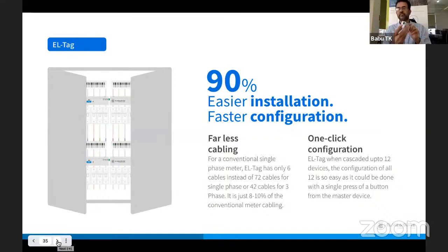Now on another side, you will find a 485 2-pin port. So you can loop several of these through and connect it to the master meter 485 which I showed you. Now look at the cabling. If you were to talk about 9 single channel meters placed in a panel and do the wiring, you will have about 72 cables moving around for these 9 individual channels of meter. As against this, one has only 4 on the voltage, 2 on the 485. If you talk about three-phase information, even then you needed 42 cables, whereas here you're only having 6 things. That 6, when I say it's pluggable, is very simple to do. You don't make a mistake of whether you are connecting the voltage connection or the current, that mismatch will not happen at all.